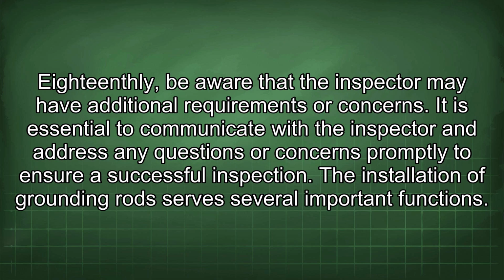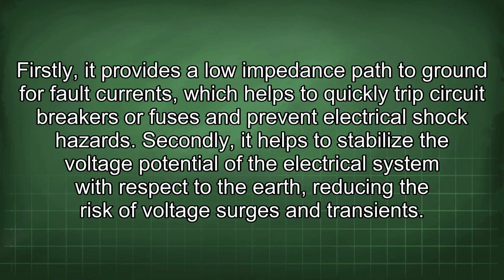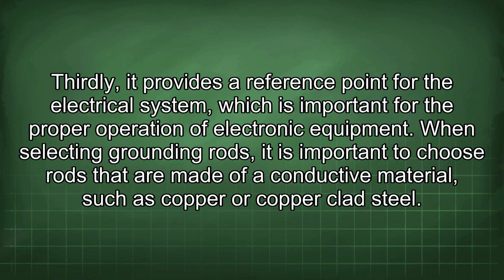The installation of grounding rods serves several important functions. Firstly, it provides a low impedance path to ground for fault currents, which helps to quickly trip circuit breakers or fuses and prevent electrical shock hazards. Secondly, it helps to stabilize the voltage potential of the electrical system with respect to the earth, reducing the risk of voltage surges and transients. Thirdly, it provides a reference point for the electrical system, which is important for the proper operation of electronic equipment.